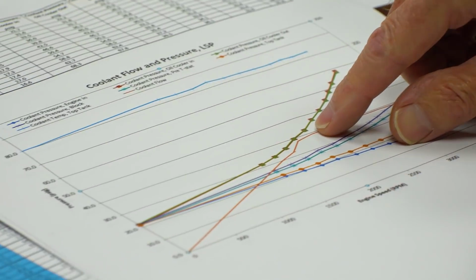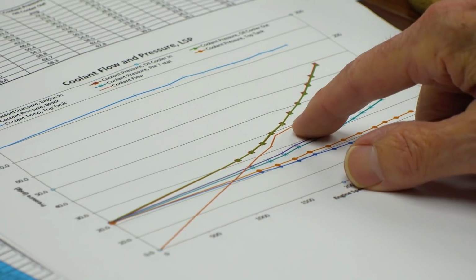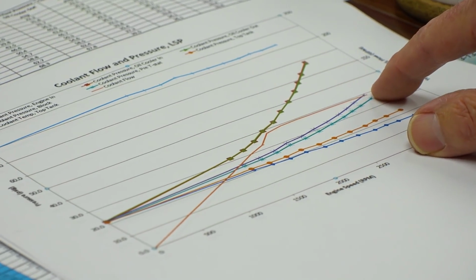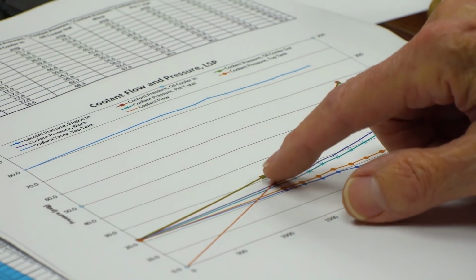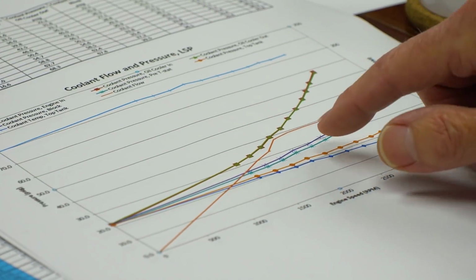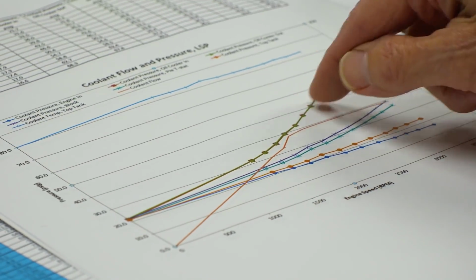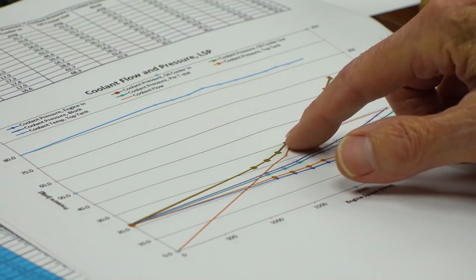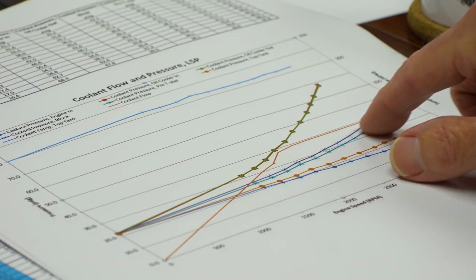Where the up pipe is, it has a factory heat shield, but we need some more heat shielding there to stabilize the temperature on those pressure sensors. But here's what's happened. That's 100 gallons per minute right there, and at about, what, 2,400? Yep. We flatline. But the pressure is going up. So these two don't go together. That's for sure. You can't be doing this with pressure and there's no more flow.